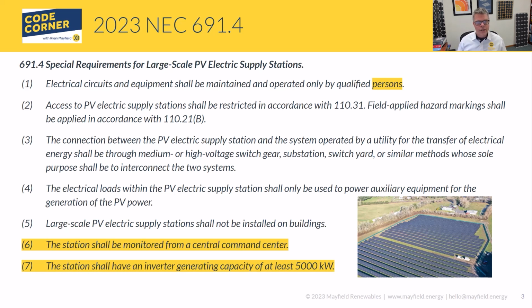And then finally, the station needs to have an inverter generating capacity of at least 5,000 kilowatts, or 5 megawatts. Generating capacity has a definition in Article 100 - that's the cumulative AC output of your inverters at 40 degrees C. So that needs to be at least 5 megawatts.